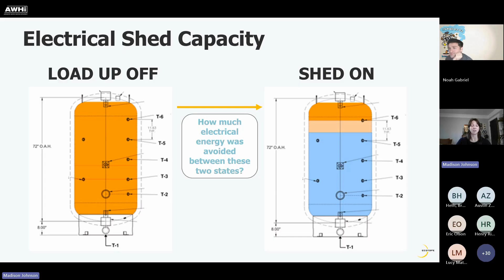Now I'll discuss a couple of case studies and show some new load shifting field data. We conducted pre-monitoring load shift tests at three new monitored sites. The first is a QAHV in Portland. For this site we had the advantage of prior demand response testing with the QAHV, but it's a new build that's been slow to occupy, so we're not yet seeing full domestic hot water usage loads. This one is still in progress.